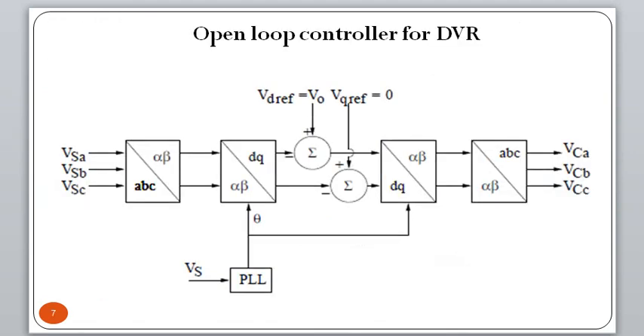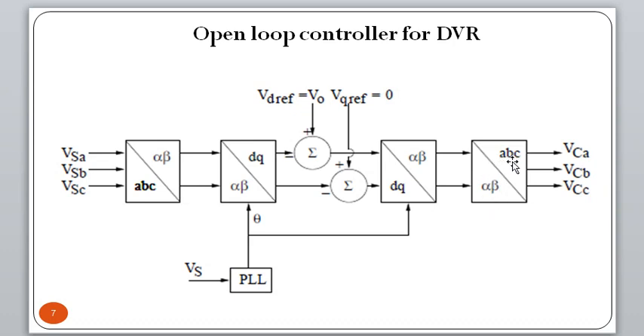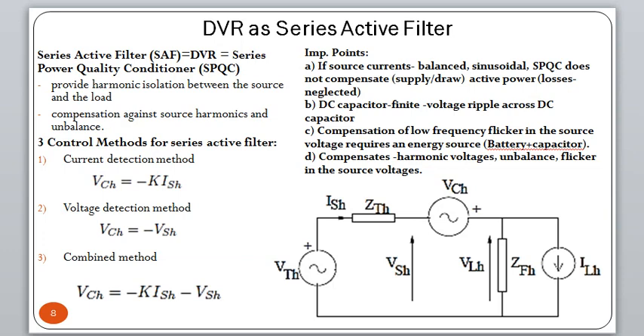For the DVR open-loop controller: the three source voltages are transformed from ABC domain to the alpha-beta domain using the Clark transformation, then converted to the dq0 domain. A PLL provides the theta signal. Reference voltage signals are derived in the dq domain, and the synchronous reference frame is used. Then, using inverse Park transformation, we go back to alpha-beta and then to ABC, giving the compensator ABC voltage signals needed to generate gate signals.